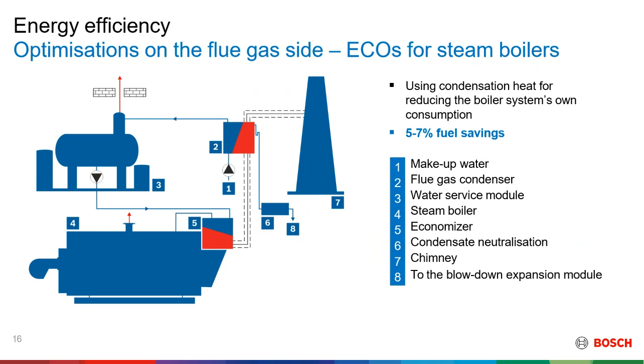So what the condensing economizer will do, after you've passed your flue gas into the normal economizer, with whichever fuel, let's say natural gas, is this: after the water has picked up some heat from the flue gas, there will still be some heat, and you can take some of it out by using a condensing economizer. Here you have feed water, either from an RO plant or a water treatment plant, flowing into a second economizer. From there, the water will flow into the feed water tank or a deaerator plant before going to the boiler, or through the first economizer.